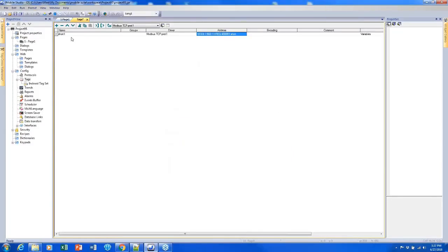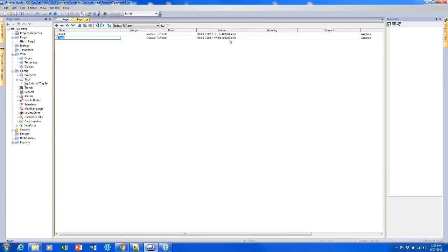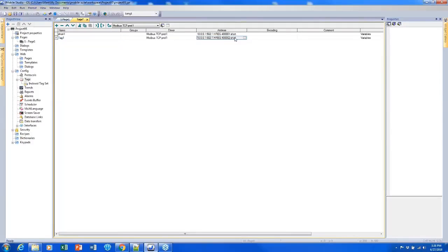The next time I create a new tag it will default to the same data type of the next offset. Since my register addressing is 16 bit, it's good that it put it to 4002 which would be the next space. However, if my first item was an integer I might need to change this to 4003 since integers are 32 bits in J mobile and shorts are 16.